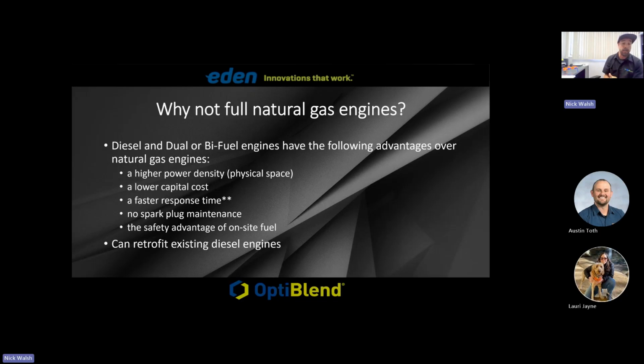You can do away with that if your engine is dual fuel. Again, there's no gas on startup, so you retain that response time, get on the bus nice and quick, and don't have to shed load to full gas engines. You just run the engine in the heart of the range, at 30 to 70% load, and you're getting good displacement of the diesel.